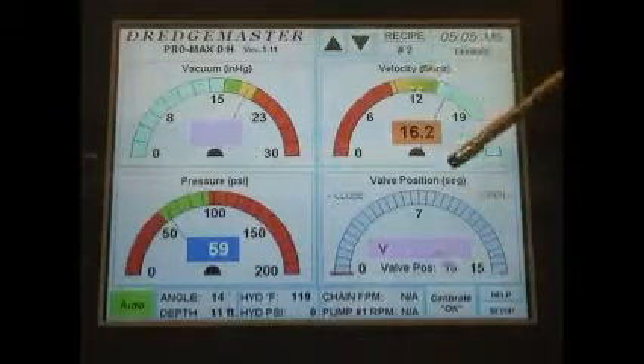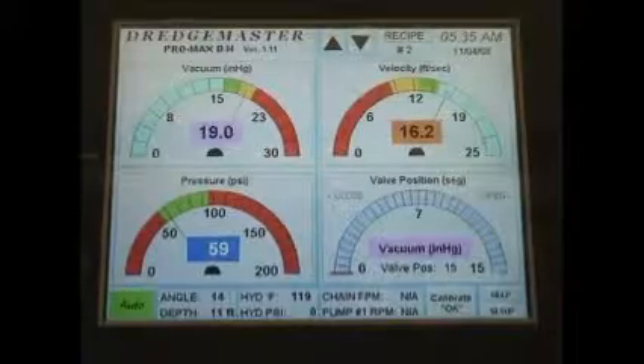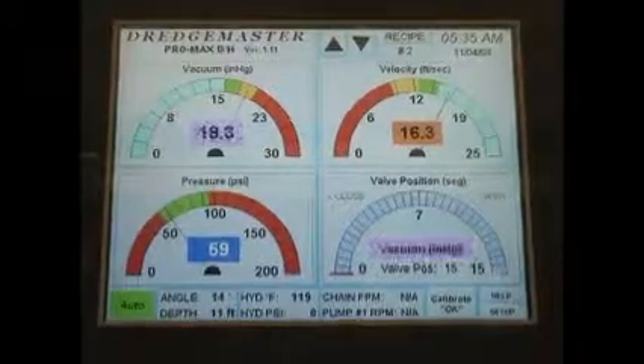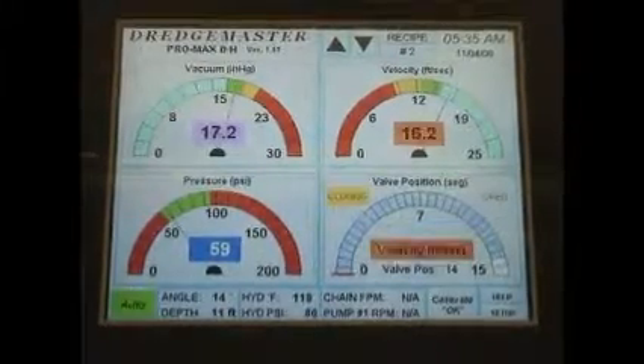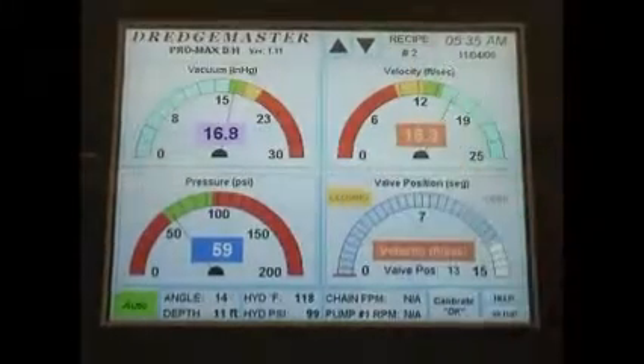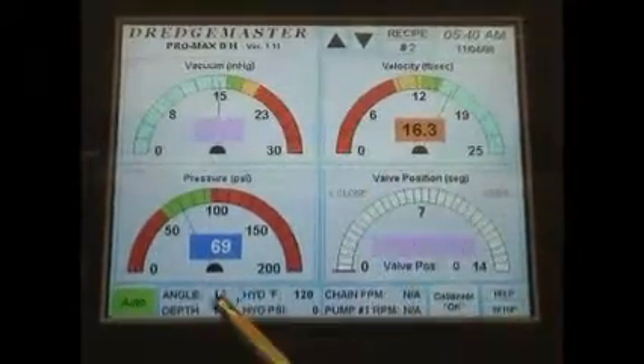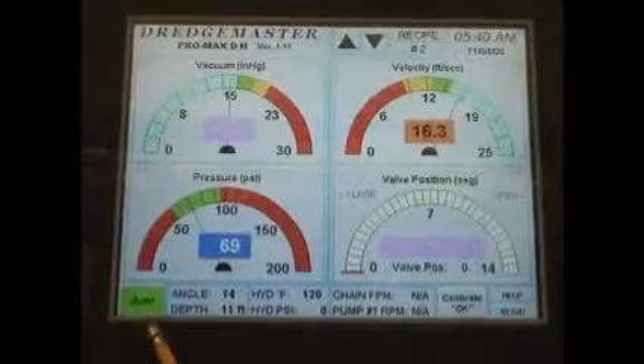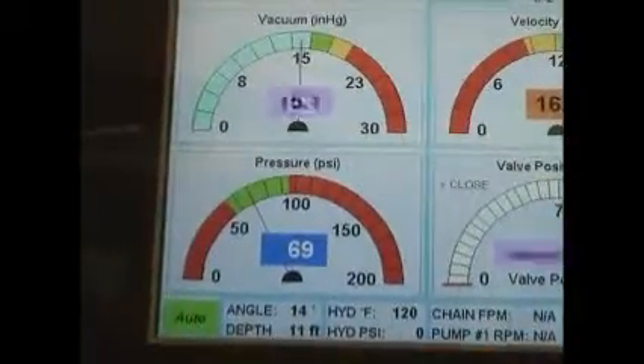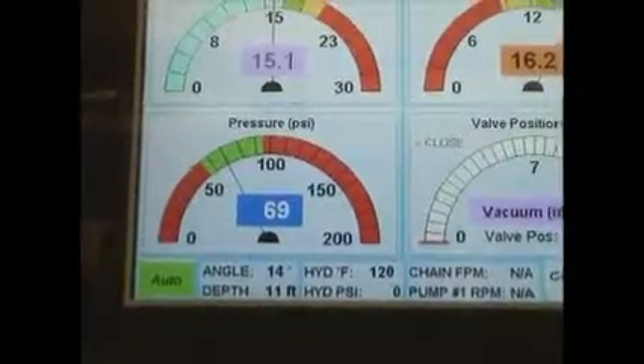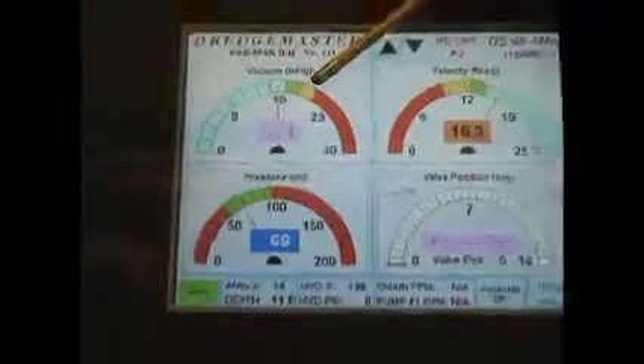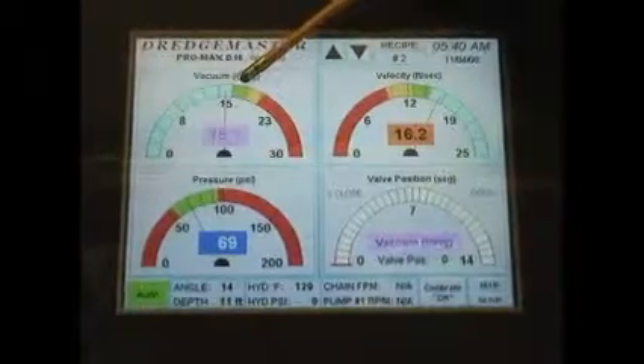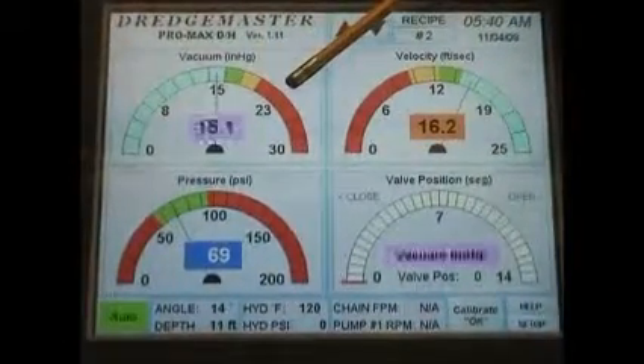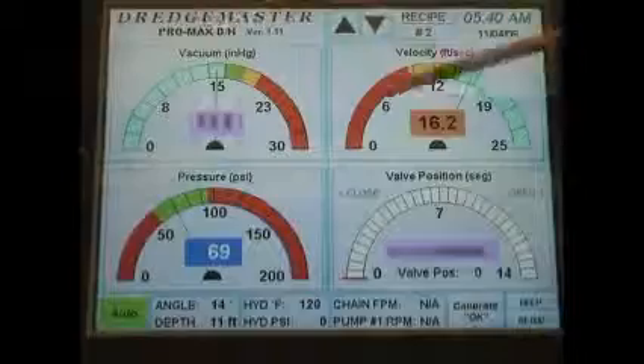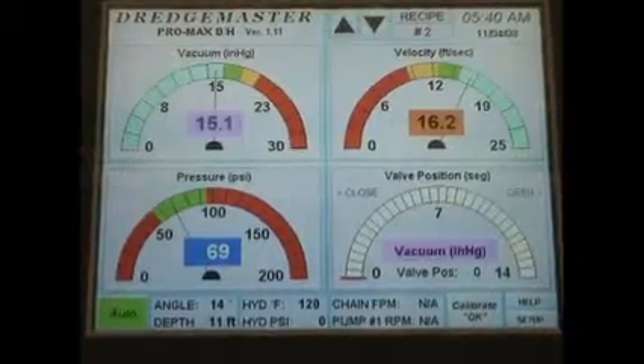So the operator has the ability to select different recipes instead of going in and making all individual changes to the color parameters. One of the buttons we have in the lower left hand corner is currently we are running in auto, which the valve is going to automatically open and close based on what, if it gets into the yellow, back into the green, it's going to open and close. If it gets into the red zone, it's going to fully extend. That's the automatic portion of the valve.